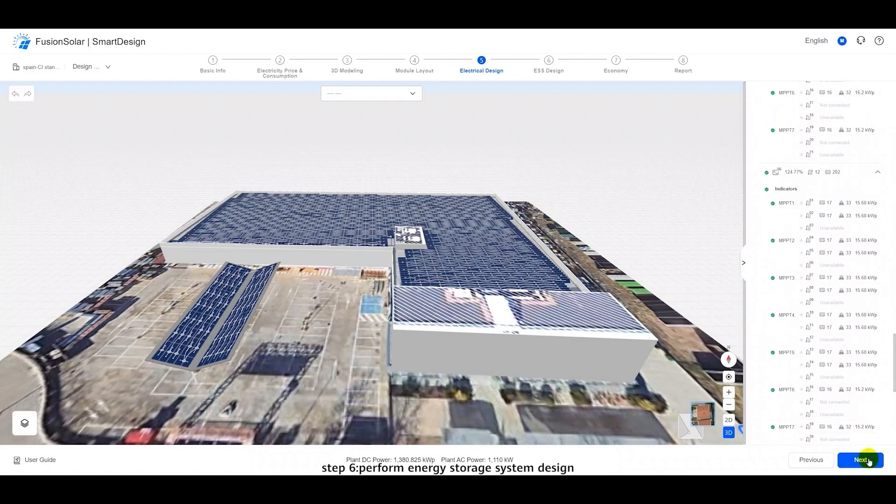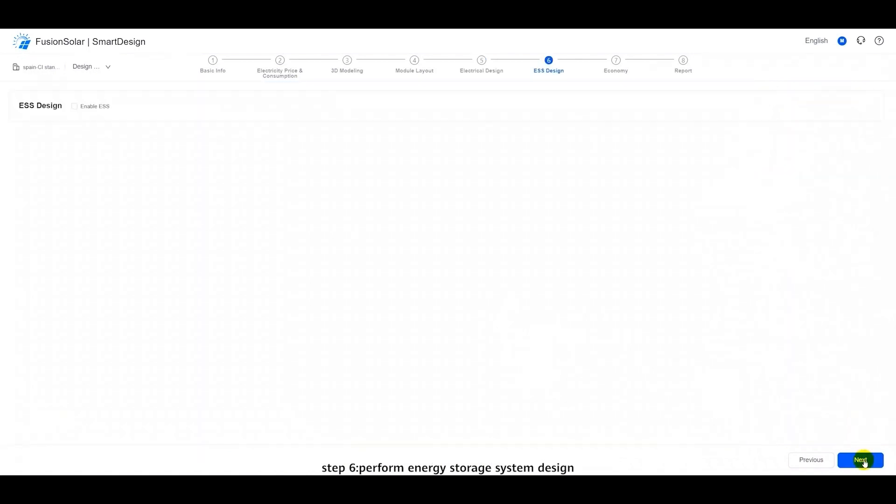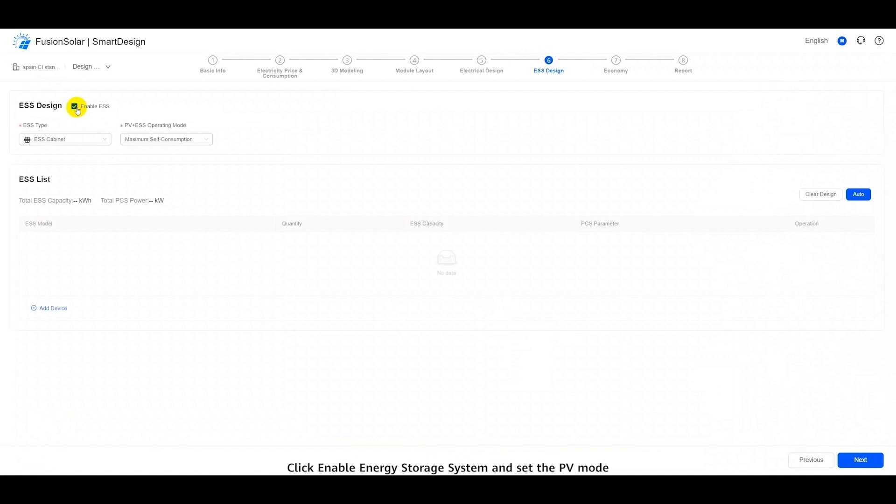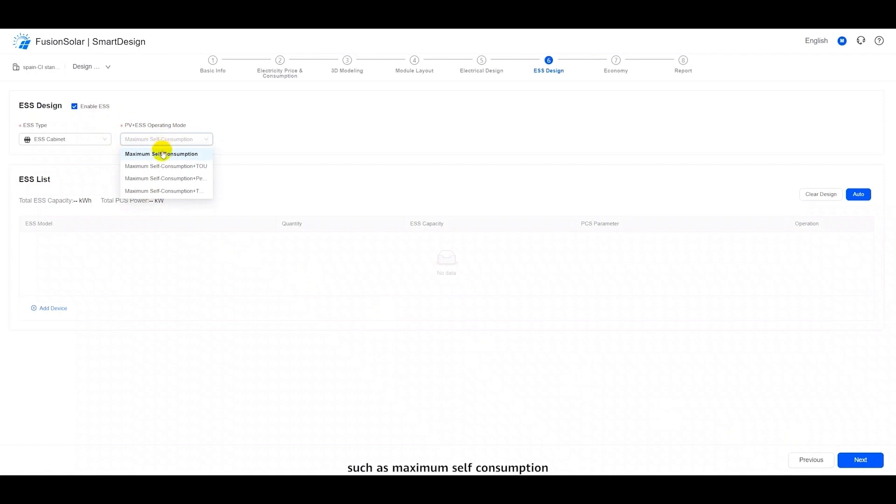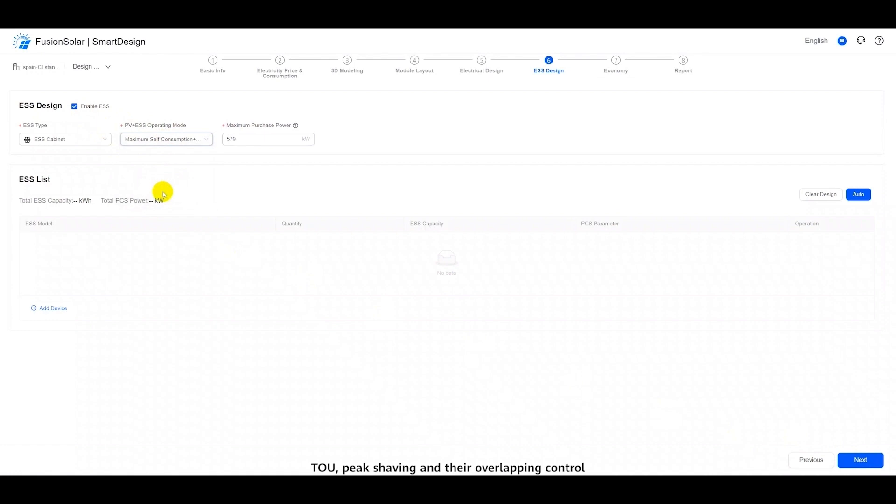Step six, perform energy storage system design. Click Enable Energy Storage System and set the PV mode. Currently, the system supports multiple operating modes, such as maximum self-consumption, TOU, peak shaving, and their overlapping control. Click Automatic Design.